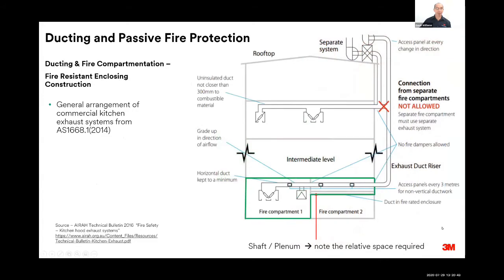Here's an example of kitchen exhaust. We've got the fire compartment where the kitchen is, fire compartment 1, adjacent to fire compartment 2, but in order to get the exhaust gases from cooking out of the building, the duct needs to pass through fire compartment 2. The solution then is to create a barrier, a compartment around the duct, to effectively continue fire compartment 1 all the way out of the building. So fire compartment 2 is not affected by any actions from that ductwork.